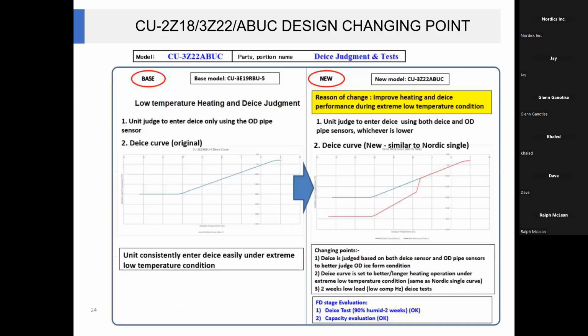We have improved our defrost cycle. Basically, we have now made 2 sensors to watch the temperature of the coils between the top of the coil and the bottom of the coil. Whichever sensor reads the lowest temperature for more than 3 minutes, we will get our first defrost cycle after 60 minutes. And then our second defrost cycle will only happen after 45 minutes.